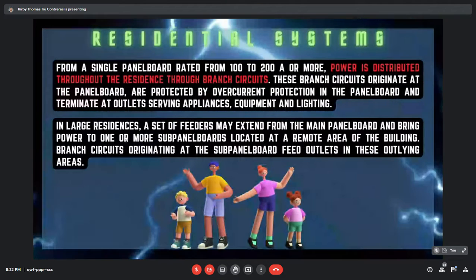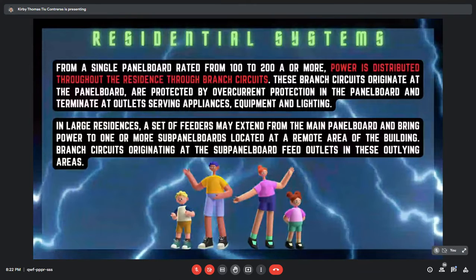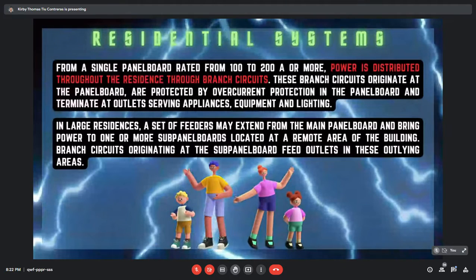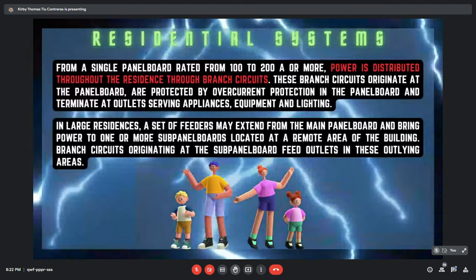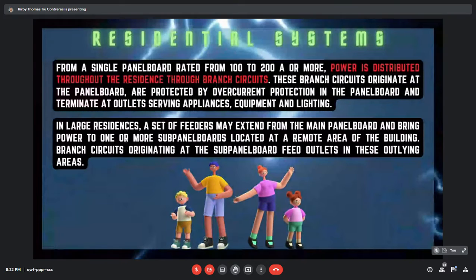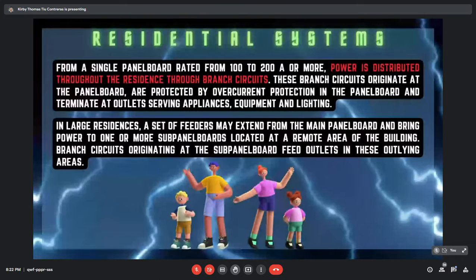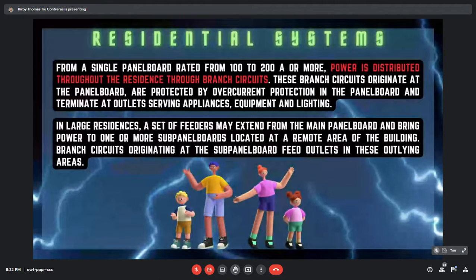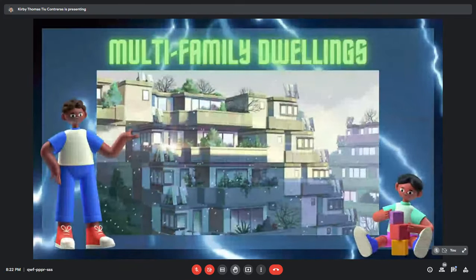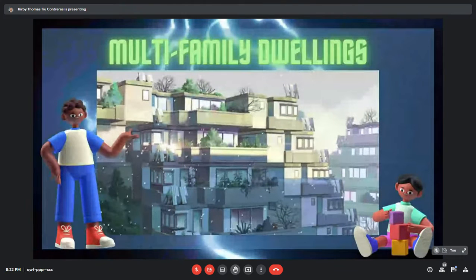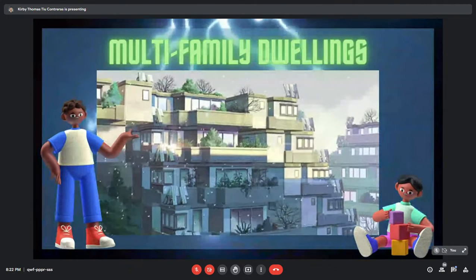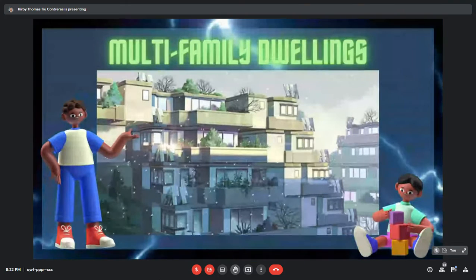Thank you. In large residences, a set of feeders may extend from the main panel board and bring power to one or more sub-panel boards located at a remote area of the building. Branch circuits originating at the sub-panel board feed outlets in these outlying areas. Next slide, please. The second type is multi-family dwellings. Examples of these are apartments and condominiums. Next, please.